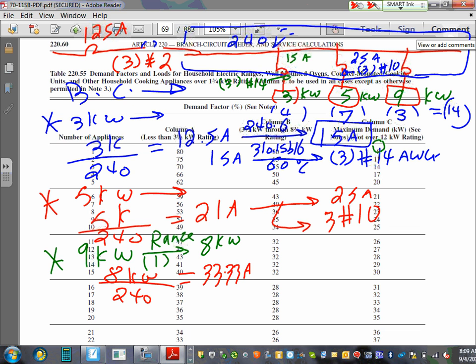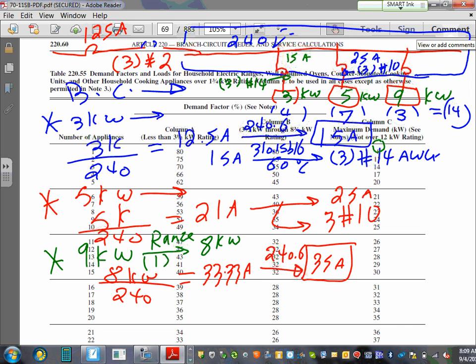33.33 amps. Okay. What's my next overcurrent device? 240.6. 35 amp. Okay. I'm gonna warn you a little bit here. Okay, so then, what's the conductor size? Everybody's going, know where we're going? 310.15(B)(16). So when you go to the conductor size, 310.15(B)(16), that will be 3 conductors, number 8. I'm not derating the neutral. 3 conductors, number 8.